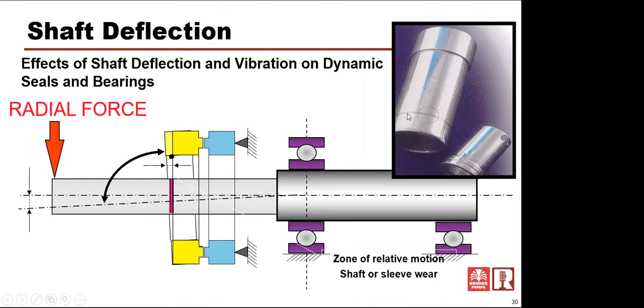Sooner or later, as that eats into it, even if these faces don't open enough to cause leakage, it's going to start leaking across that shaft sleeve fretting area.